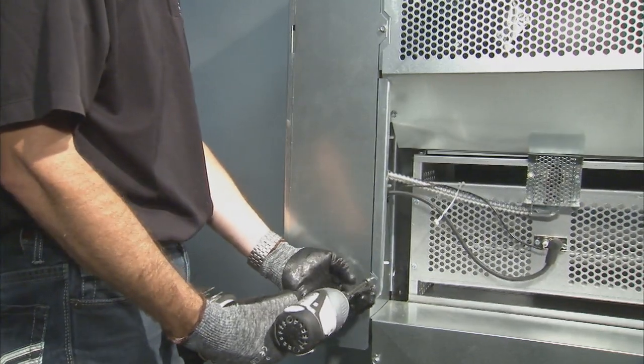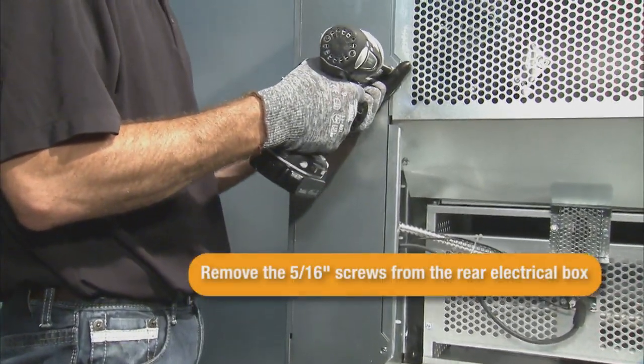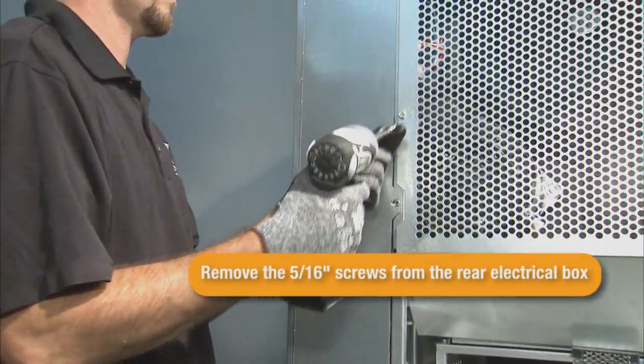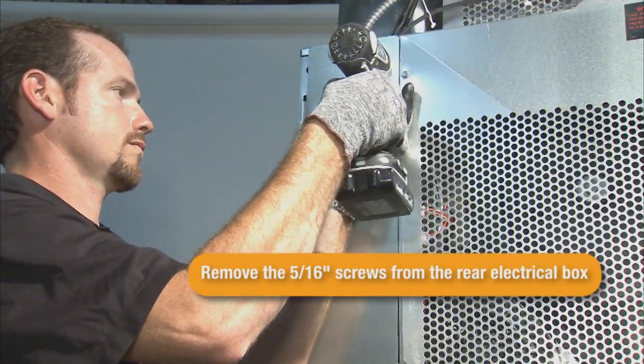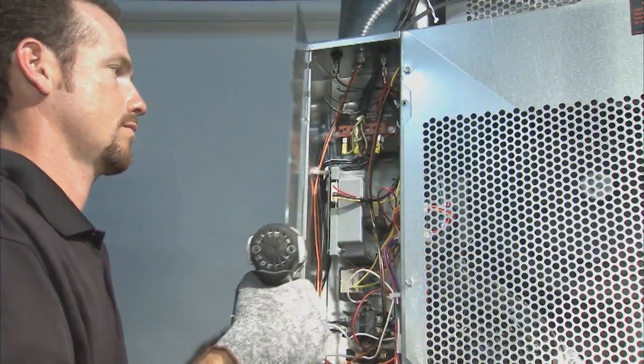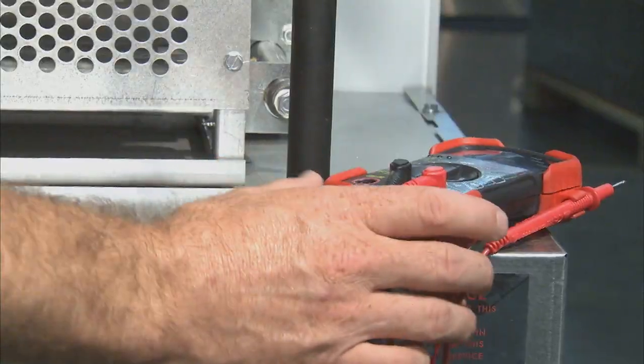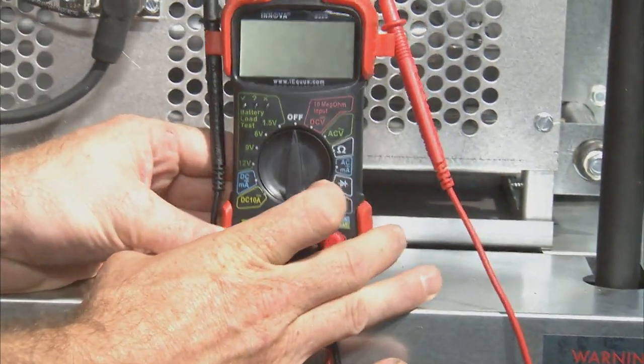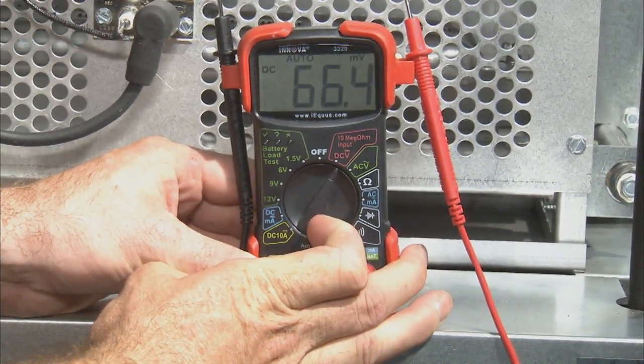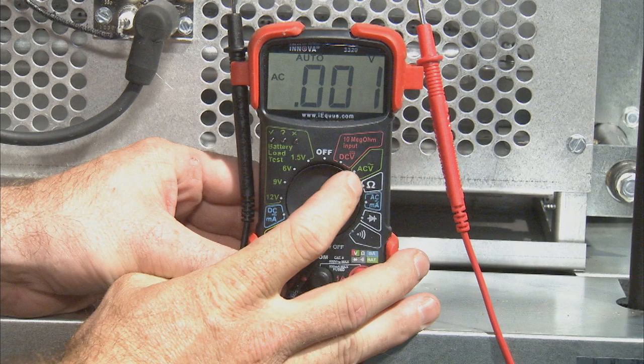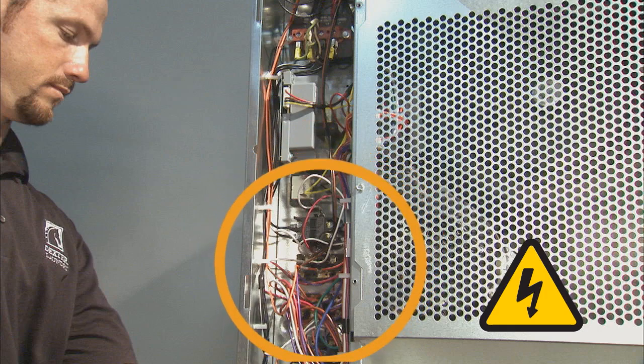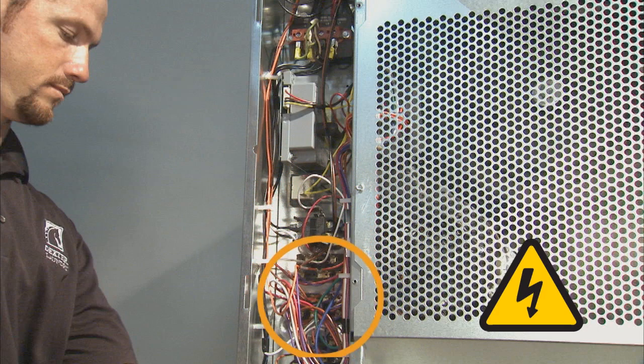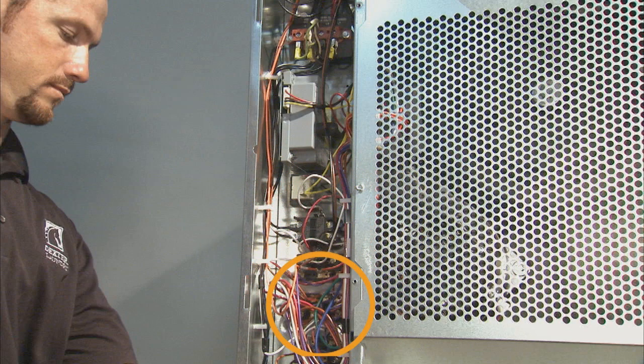Now, to begin checking voltages through the heating circuit, remove the 3 5/16 screws from the cover panel of the rear electrical box. A voltmeter will be used to test for voltage at the upper or lower terminal block in the electrical box. Set the voltmeter to a 120 volt setting. Locate the upper terminal block under the step-down transformer. If the issue is with the lower pocket, use the lower terminal block instead.